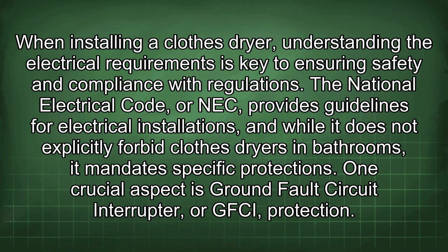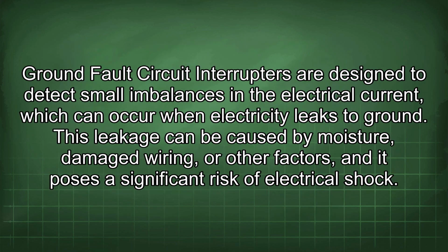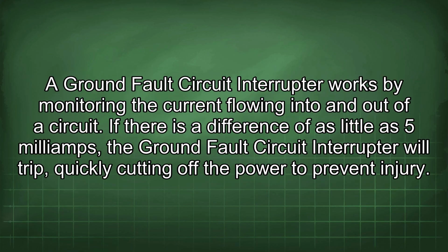One crucial aspect is ground fault circuit interrupter, or GFCI, protection. Ground fault circuit interrupters are designed to detect small imbalances in the electrical current, which can occur when electricity leaks to ground. This leakage can be caused by moisture, damaged wiring, or other factors, and it poses a significant risk of electrical shock. A ground fault circuit interrupter works by monitoring the current flowing into and out of a circuit. If there is a difference of as little as 5 milliamps, the ground fault circuit interrupter will trip, quickly cutting off the power to prevent injury.